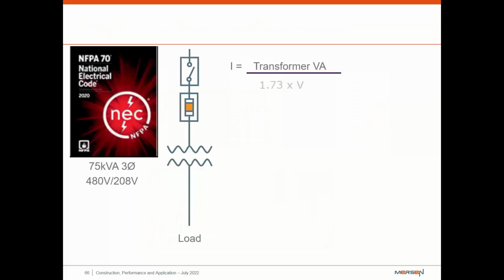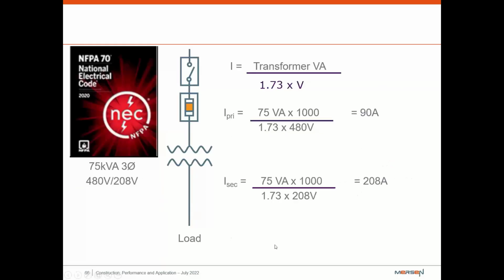So let's get into the fun part with some math. We have a 75 kVA three-phase 480 volt transformer. So we're going to try and determine what the actual current output on this is going to be. So you take your transformer VA, multiply it by 1,000, divide it by the square root of 3 multiplied by 480, and you're going to get around 90 amps on the primary. So on the secondary, you're going to get 75 kVA multiplied by your 1,000. And then you're going to divide that by the square root of 3 multiplied by the secondary voltage. So you get about 208 amps.